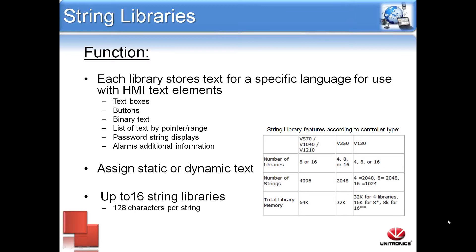A program can have up to 16 libraries depending upon which controller is being used. By default, controllers start with four or eight libraries. If using a V130, increasing the number of libraries will reduce the memory by half each time it is doubled. Each string within a library can contain up to 128 characters.